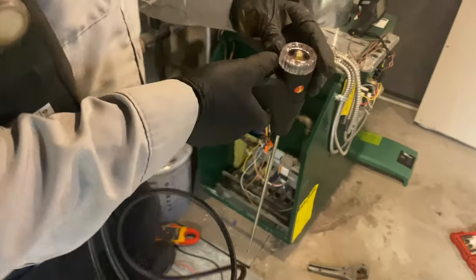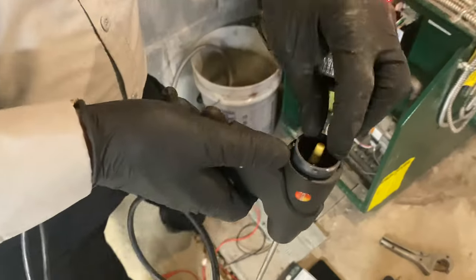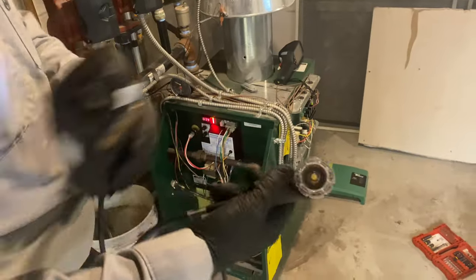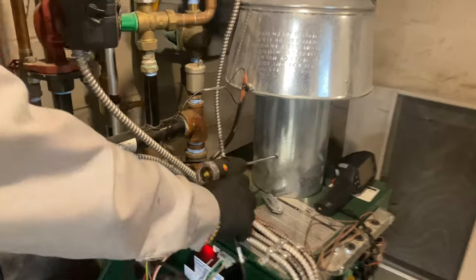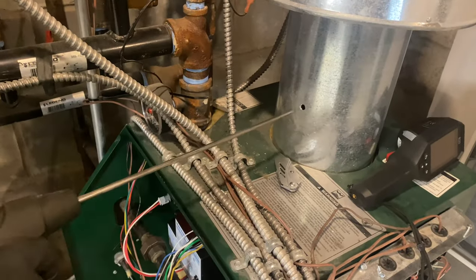The first thing you need to make sure, especially if it's ice cold outside, make sure there's no ice or anything in there, no liquids, frozen, or anything damaged. Make sure everything's intact, like this is in place, right? And this probe, see right there—it's going to go halfway into the flue, not all the way in, not all the way out.